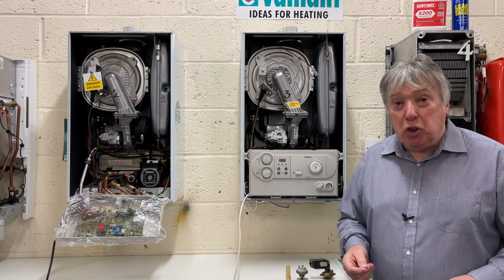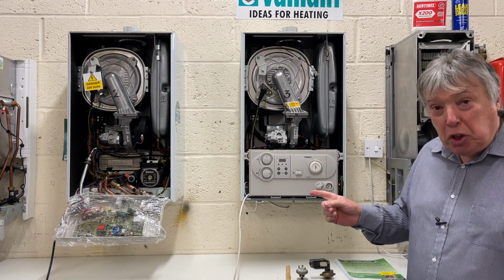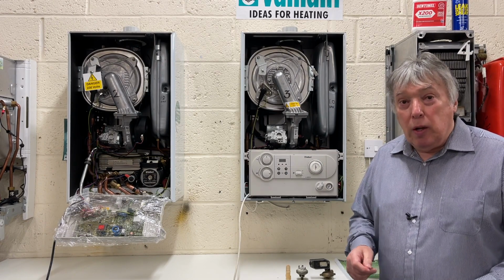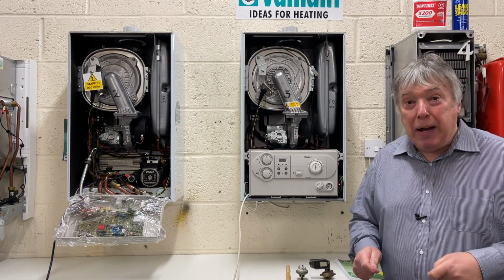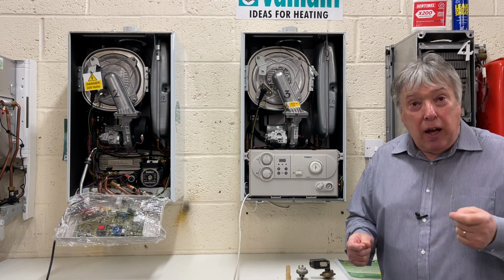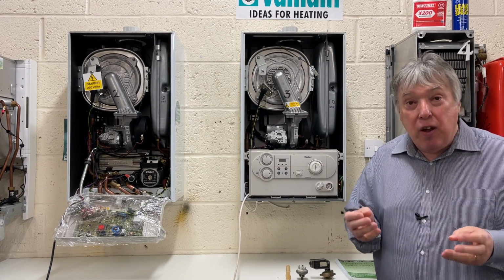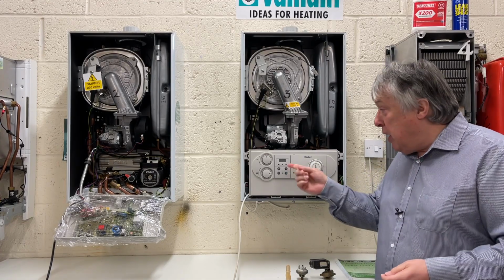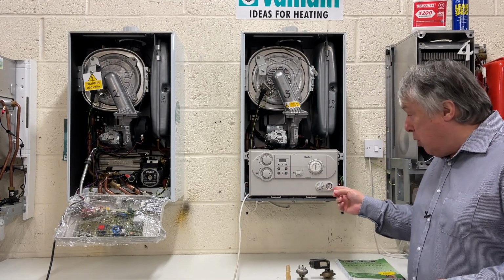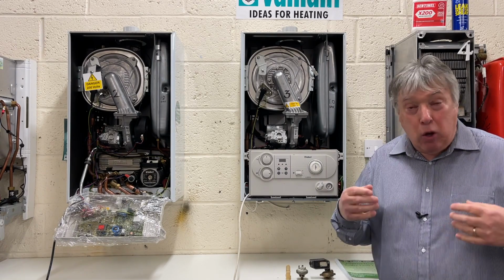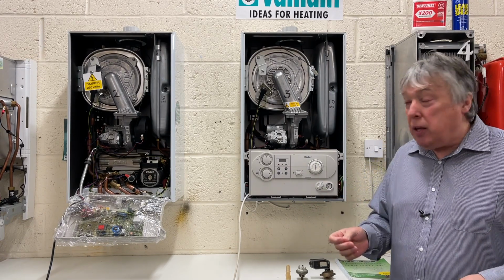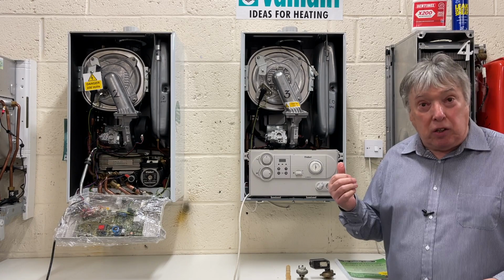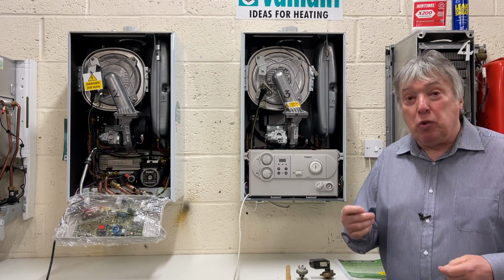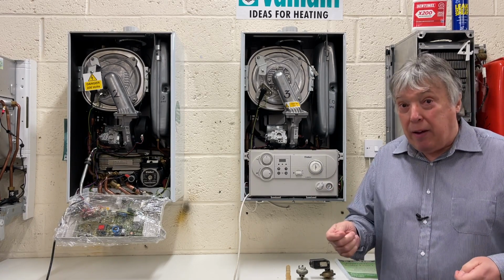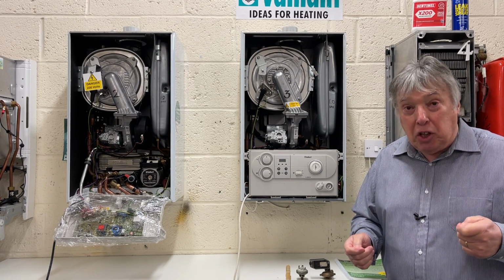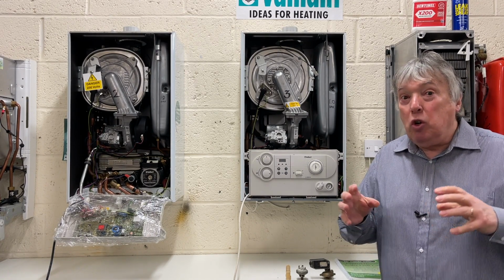But if we concentrate on just the low pressure F22, no manufacturer can put into the manual all the different faults and the errors surrounding that particular fault. Vaillant will say low pressure, which it may well be, and it usually is, as they all will do that. But they also put in there that maybe the pump is seized up or the lead goes to it. Other manufacturers will say, oh, also look at this or that. So what I'm trying to teach here for engineers is to look outside the box.